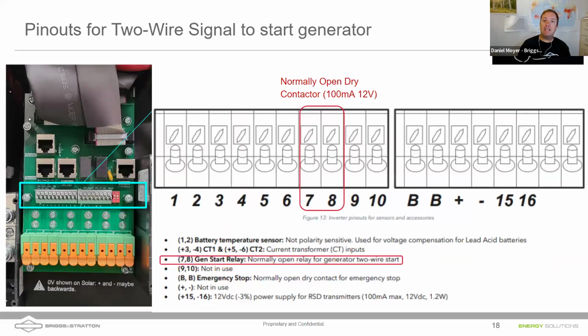So when we look at that accessory pinout, one of the ones we're going to focus on in this talk is how to wire up that automatic generator start. We do have a normally open two-wire signal on our Briggs & Stratton Energy Solutions generators. So on the Solarc side, it's going to be pins 7 and 8. That's what we're going to run over to our generator and then be able to start up that generator as well.